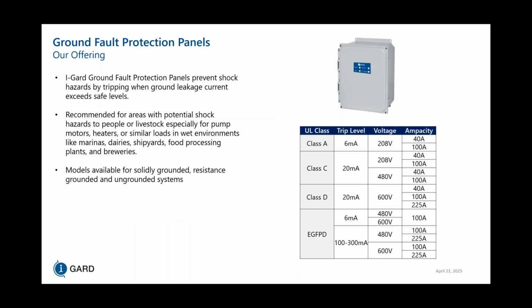At I-Gard, we have ground fault protection panels that prevent shock hazards by tripping when ground leakage current exceeds safe levels. It's recommended for areas with potential shock hazards to people or livestock, especially for pumps, motors, heaters, or similar loads in wet environments like marinas, dairies, shipyards, food processing plants, and breweries. There are models available for solidly grounded, resistance grounded, and ungrounded systems, and the table here indicates our offering. We actually have two variants. One has a 100 amp breaker and one has a 225 amp breaker, and we have adjustable trip levels between 6 milliamps and 300 milliamps.